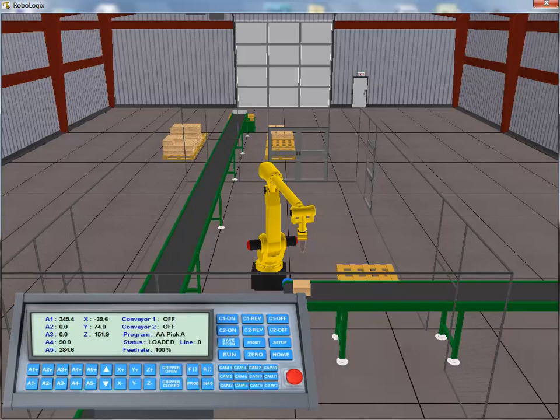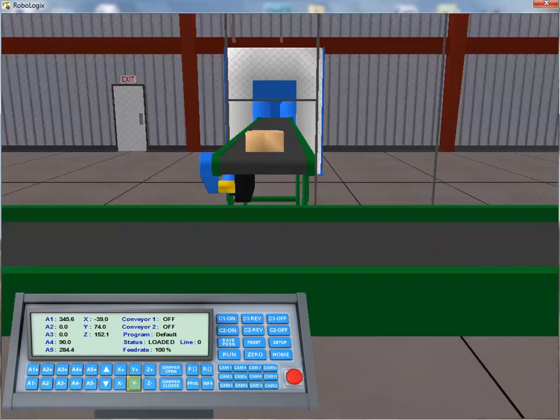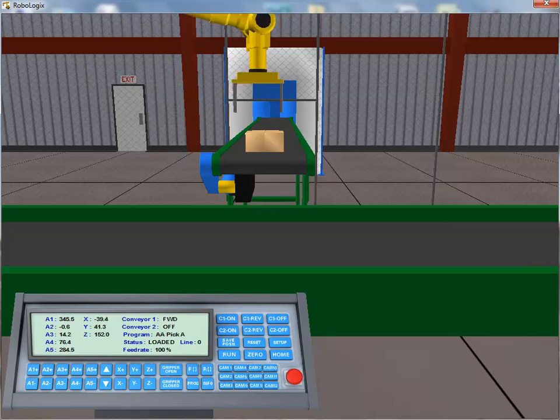We click on the main button to return to the main view, then click on the Camera 9 button to get a better view of our next target location. We use the Linear Motion Y minus button to bring the tool center point into view with this camera angle. The Y plus and Y minus jog buttons move the tool center point linearly up and down. Now that we have the tool center point in view, we can clearly see that it's not aligned with the box. We use the Z plus and minus buttons to move the tool center point left or right. In this instance, we need to move the center point to the right by clicking the Z plus button a few times.